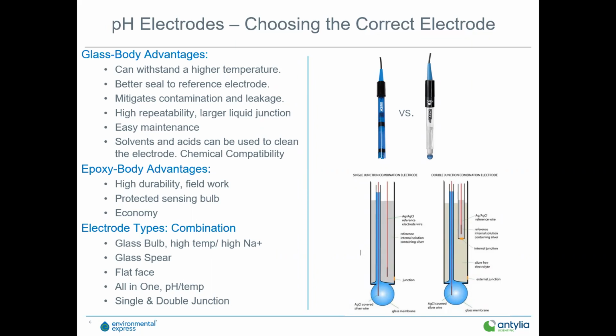So electrode types, some of the specialty combination electrodes that we offer. And by combination, I mean each of the electrodes has the reference part of the sensor built into it, as well as the measuring part of the sensor. I'll date myself: when I was first trained, we actually had a separate reference electrode and a separate measuring electrode. Nowadays, they're all combination electrodes with those two electrodes built into one unit. So glass bulb, high temperature electrodes, high sodium electrodes, glass spear, flat face, all in one. That's a pH electrode with a built-in temperature sensor, and then single and double junction electrodes as well.